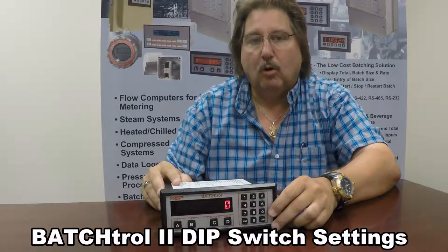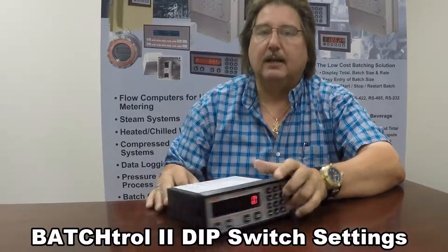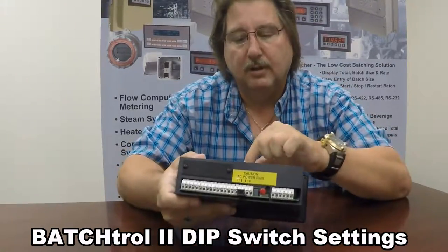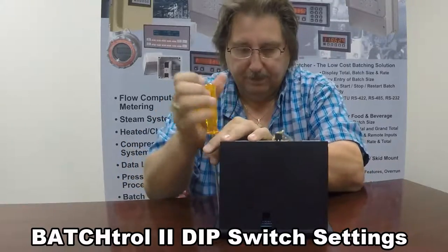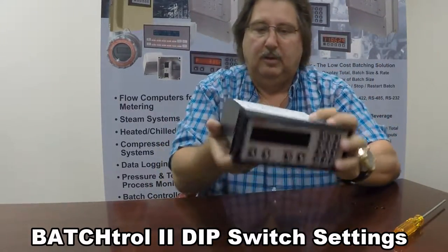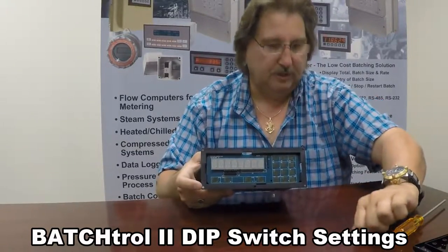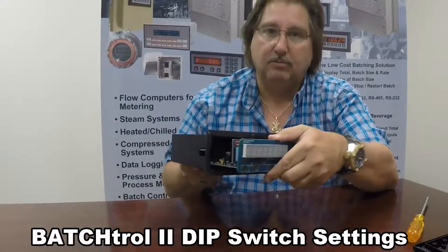If you're using a Hall Effect sensor, what you will need to do — and I'll show you in this video — is to disconnect the power first from the back of the BATCHtrol II. Like so. You then have to remove the six screws that are around the bezel of the front of the unit. Now you're going to have to remove the unit from the case. Removing those screws allows the front bezel assembly to come off like so.